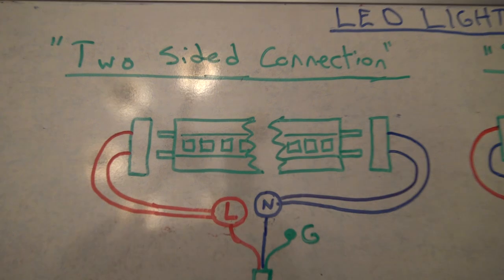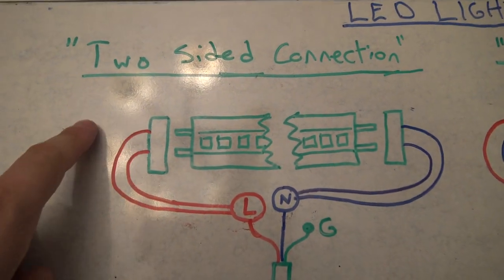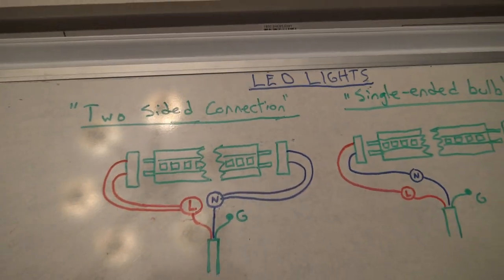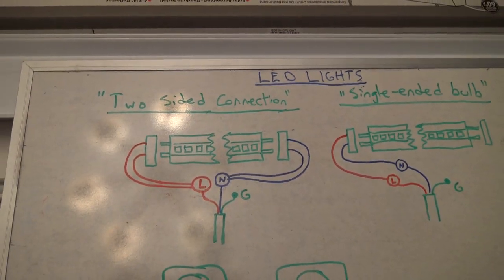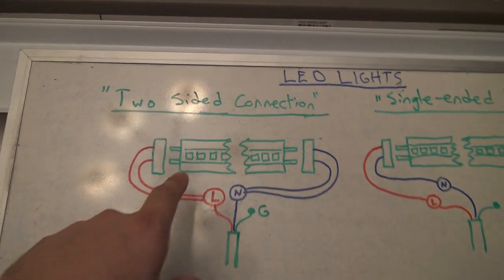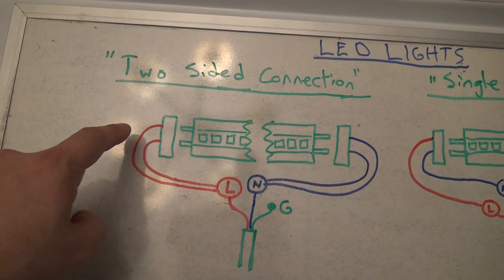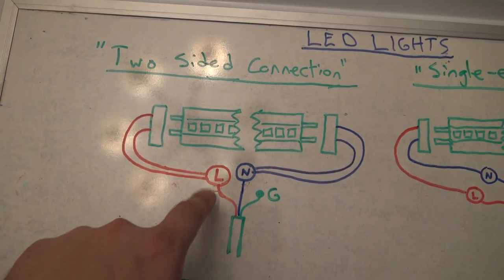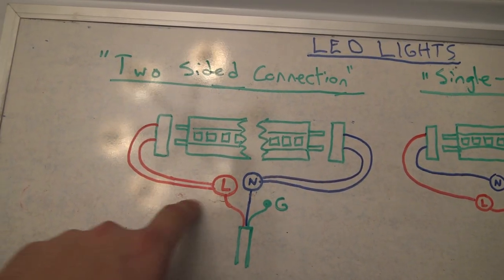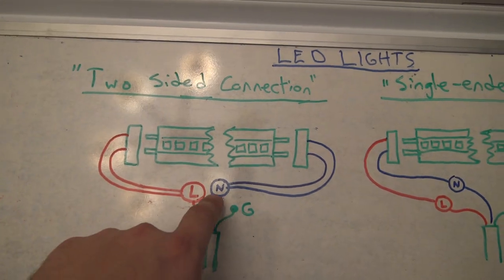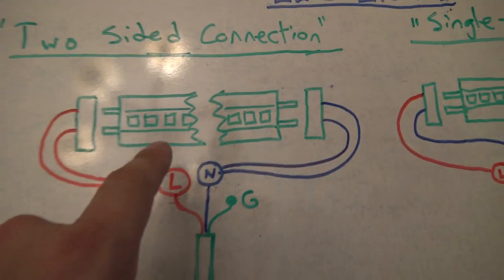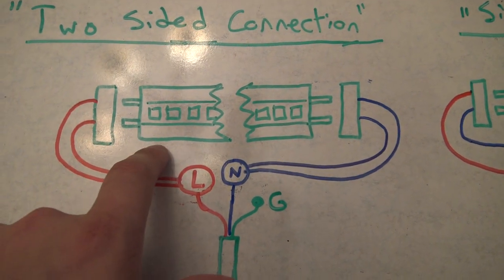But here they are. The first one is a two-sided LED light. Sometimes it'll be called two-sided connection. Sometimes it'll be called like two-ended bulb, something like that. It basically denotes that you are taking your load on one end, and your neutral on the other end of that light. And this is per bulb.